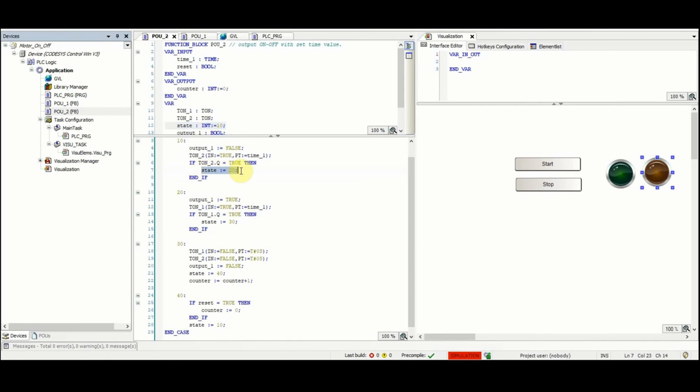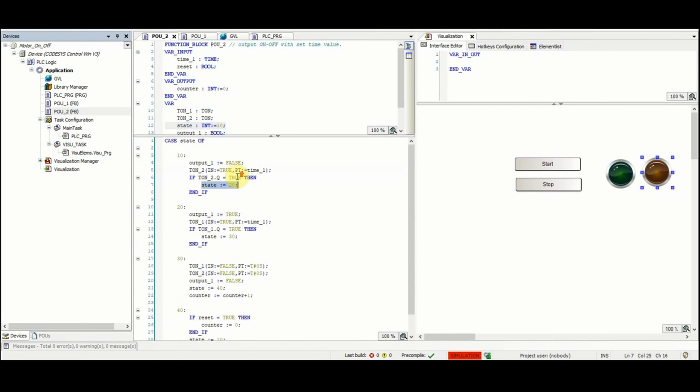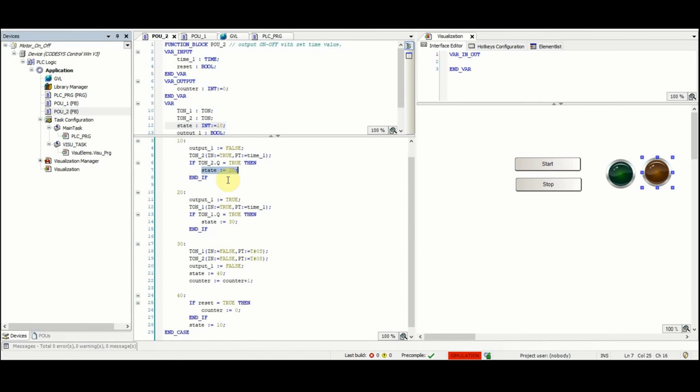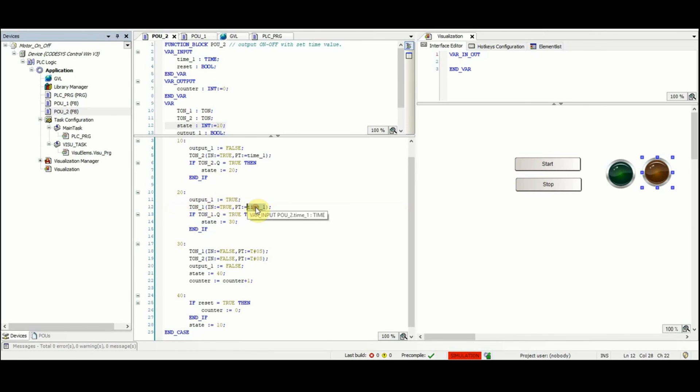When state is equal to 20, the output will be set to true, output_1. Then the first on-delay timer will be called with the same amount of preset time for the time delay, and then when the timer is done the state will be set to 30.